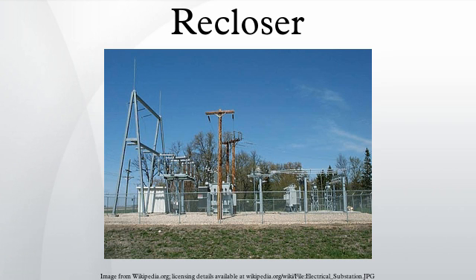This presents a major problem when dealing with transient events. For instance, a tree limb that is blown off a tree during a windstorm and lands on the line may cause a short circuit. However, the fault will quickly clear itself as the limb falls to the ground. If the only protection system is the breakers at the distribution centers, large areas of the grid would be blacked out while the repair crew resets the breakers.